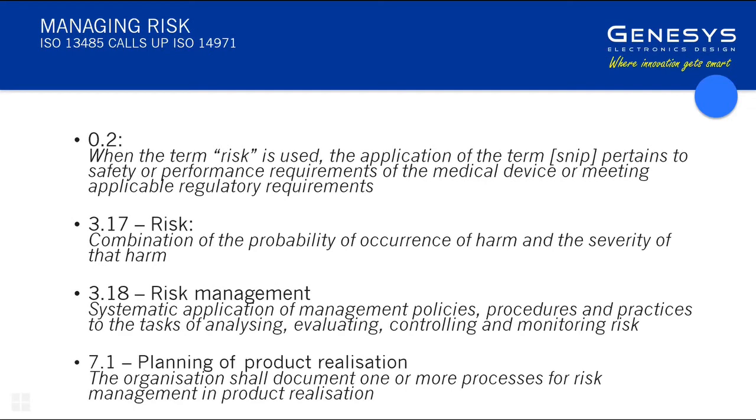If you apply it more broadly, all you're doing is building in a world of pain into the process by applying the medical risk controls to risks beyond what they're intended to address. And I've just put a couple of the definitions in there just to bring all this together. These terms are defined, and it's extremely important to understand what the definition of those terms is and means, because they are all pervasive throughout the risk management process during your design and development. These are the clause numbers in 13485.